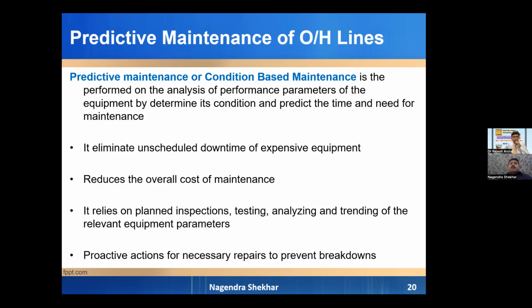Predictive maintenance, as I have already told you, eliminates unscheduled downtime of expensive equipment. Just the day before yesterday, through partial discharge, we detected tracking in an RMU, and we replaced that RMU and sent the defective RMU for repairs. And I'm very sure that if it had not been done, there could have been a fault and failure of the entire RMU. That RMU costs somewhere around 3 to 4 lakhs. Installation and repairing will be additional, transportation will be additional. So we have saved that cost. So, reduction in cost by predictive or condition-based maintenance.